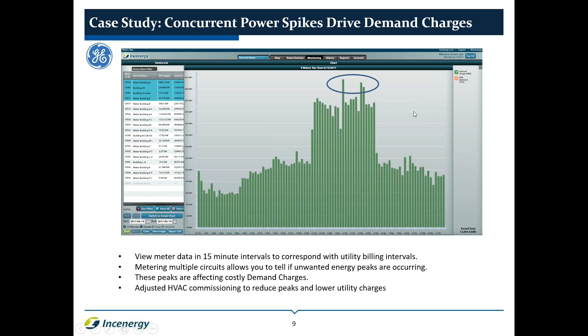One way that we do that is we will go through all the meters and see where the peaks are occurring for a group, and then we can go one by one through each of the meters and find which one is actually causing that peak, and is it possible to reduce that peak. Some ways that we can reduce the peak are cycling back equipment if it can be reduced a little bit. Sometimes we can take the HVAC systems and stagger their usage so that one will fire, then the other will fire, then the other will fire. By doing these things, we can level off these peaks and cause a reduction in your utility bill.